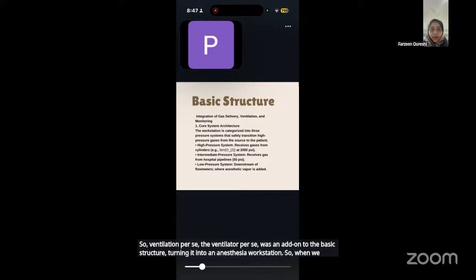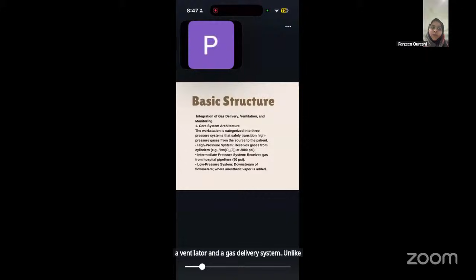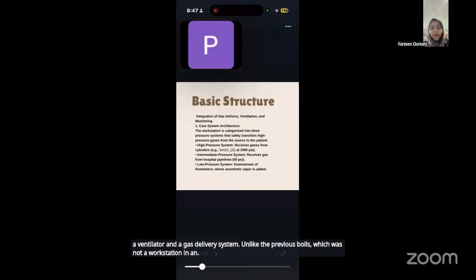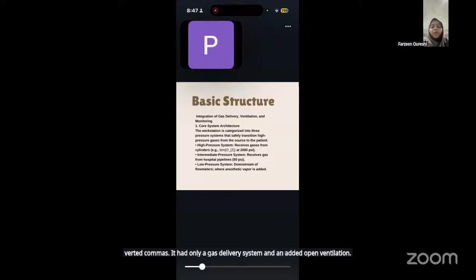turning it into an anesthesia workstation. So when we call it a workstation, what do we assume? We assume a small monitoring system, nowadays including end-tidal carbon dioxide, which is a basic ASA monitor now, a ventilator, and a gas delivery system. Unlike the previous Boyle's, which was not a workstation in inverted commas, it had only a gas delivery system and an added open ventilation with almost no monitoring. So the core system remains the same.